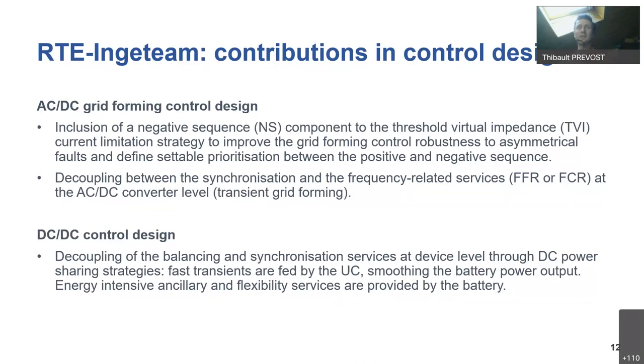There is also the control that has been decoupled. So we have this grid forming control that can be delivered for just a few seconds and is completely decorrelated from traditional frequency services. We call that transient grid forming, but it does not require a lot of energy to be stored, and it still stabilizes the grid. We also have a specific DC-DC control design that allows each kind of storage to deliver the services that it is best suited for. For example, the ultra caps can deliver the fast transients, while the battery can do the energy-intensive ones.